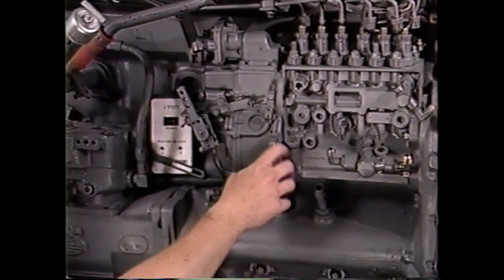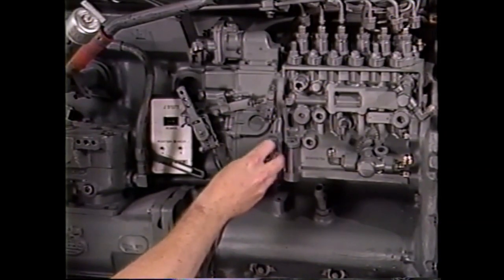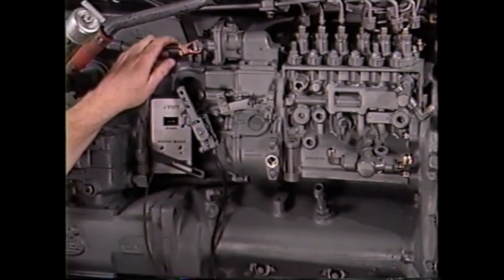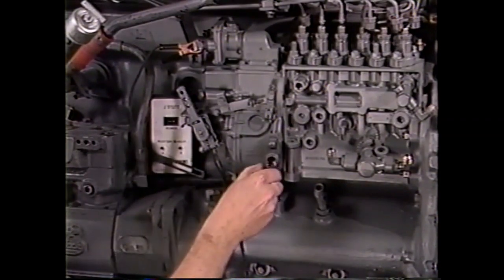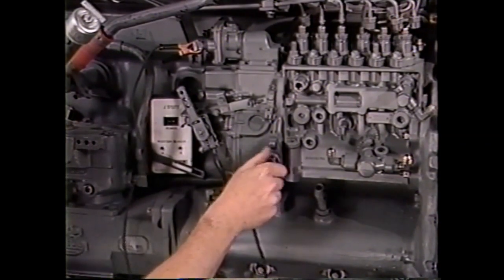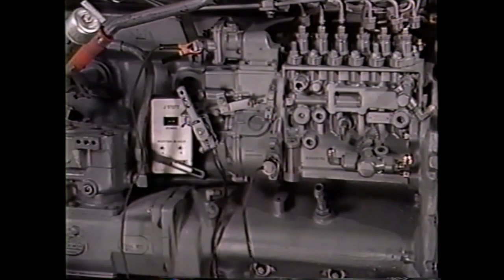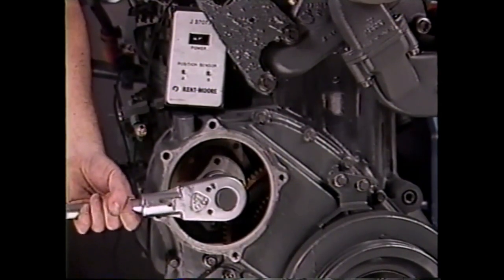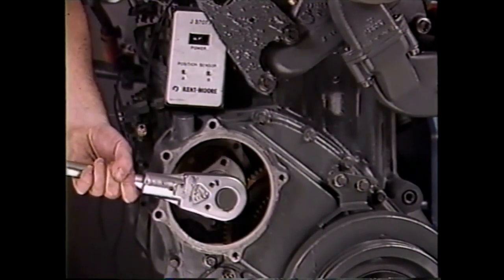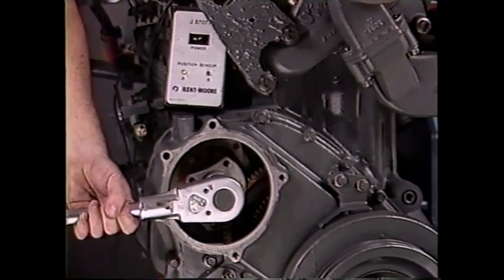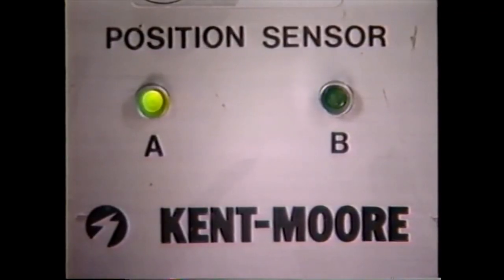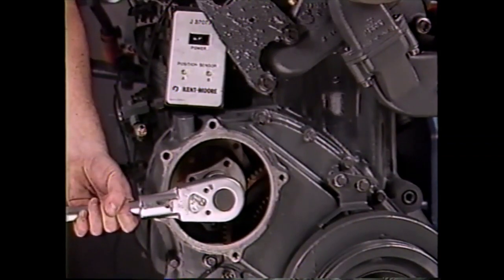To install the position sensor, remove this plug from the back of the pump, clip the ground clamp to a good ground, and screw the sensor probe into the threaded bore. Next, turn the drive hub nut on the pump until both indicators on the sensor light in the proper sequence. A first, then B. A special hub rotation tool isn't required.